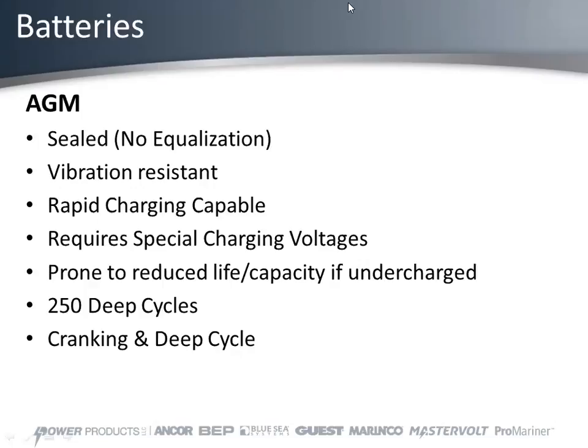There's a couple ways to address that. In our chargers there's an option to equalize. You turn off all your loads and it brings the voltage up to 15.5 volts per battery. That will break some of that sulfation off the plate, but it's kind of a band-aid—it's not bringing back the full capacity of the battery.